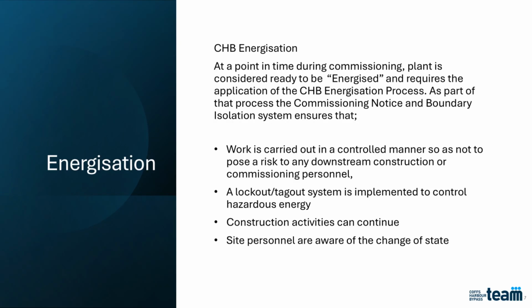At a certain point during commissioning, plant is considered ready to be energized. When this happens, the CHB energization process is applied. As part of this process, commissioning notices are issued, and the boundary isolation system is put in place. This ensures that work is carried out in a controlled way and does not create risk for downstream construction or commissioning personnel. A lockout and tagout system is used to control hazardous energy. Construction activities can continue safely around the commissioning work, and site personnel are aware that the state of the plant has changed. You must pay attention to these notices and boundaries. They signal that the plant and area now carry different risks.